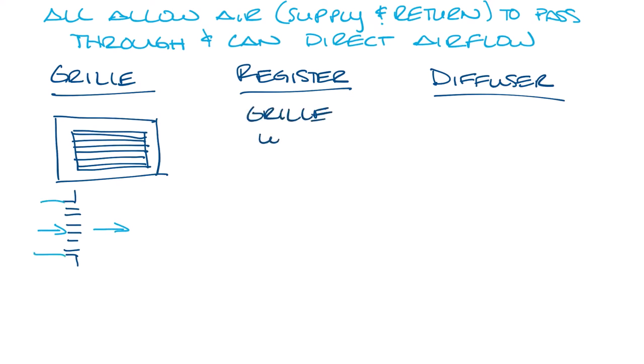Now a register is a grill with a damper. So from the front, it'd look the same, but if I draw it from the side, you would have a damper on the back of it. The air is still passing straight through the device, and the neck size and the face size are the same.